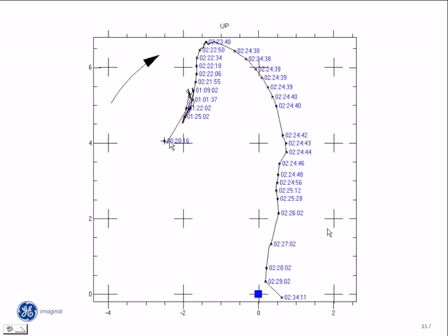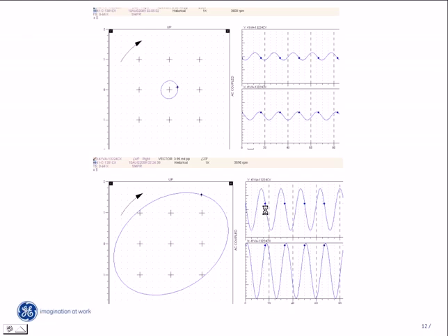Looking at a different plot, this is a plot of the shaft center line. The machine normally operates with its shaft in this part of the bearing. But by after 8 o'clock in the evening, the shaft was already high within its bearing, and over the next few hours it began to rise up in the bearing even further until the point at which the machine tripped, and as the machine ran down, the shaft dropped down within its bearing. Looking at the orbit at a couple of times, here's around 2:20 a.m., nice low vibration, but just before the trip, a very large, slightly elliptical orbit.